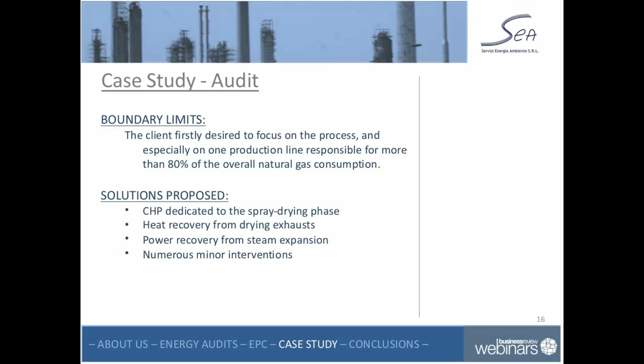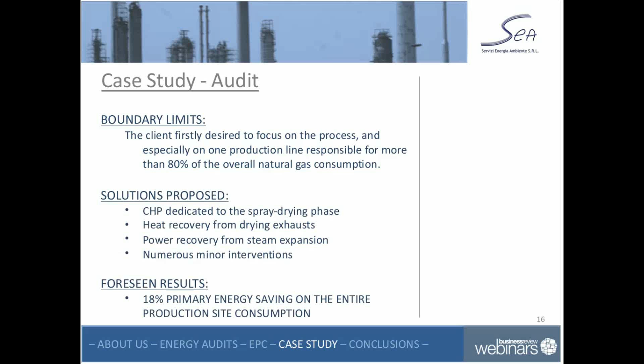We came up with a few solutions: mainly a CHP plant dedicated to the drying phase of the process, heat recovery from the drying exhausts, and power recovery from steam expansion, since steam was produced at 12 bar but used at a much lower pressure. From this expansion we would recover some power, plus a number of minor actions, bringing about 20% primary energy saving across the overall production site.